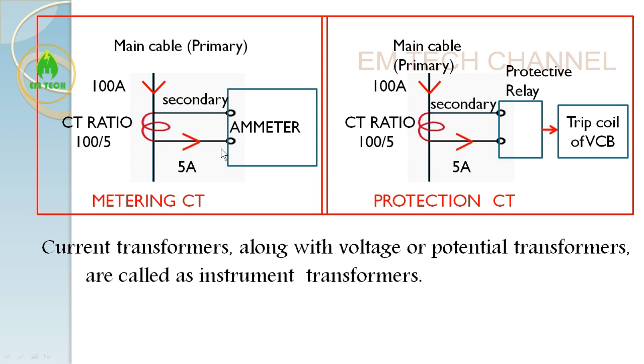Due to the CT ratio, if 100 amps is flowing in the primary, the CT will produce 5 amps in the secondary if the ratio is 100/5. This 5 amps is taken and fed to either meters, if it is a metering CT, or to protective relays, if it is a protection CT. The voltage transformer functions similarly — in a current transformer we reduce the current and feed it to meter or protection systems.